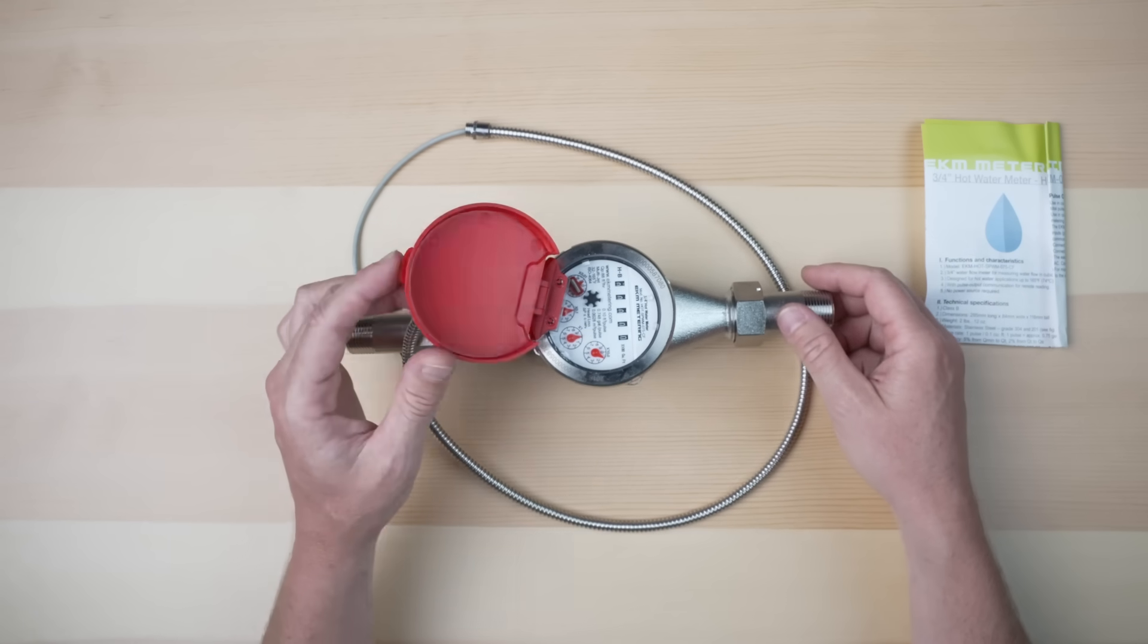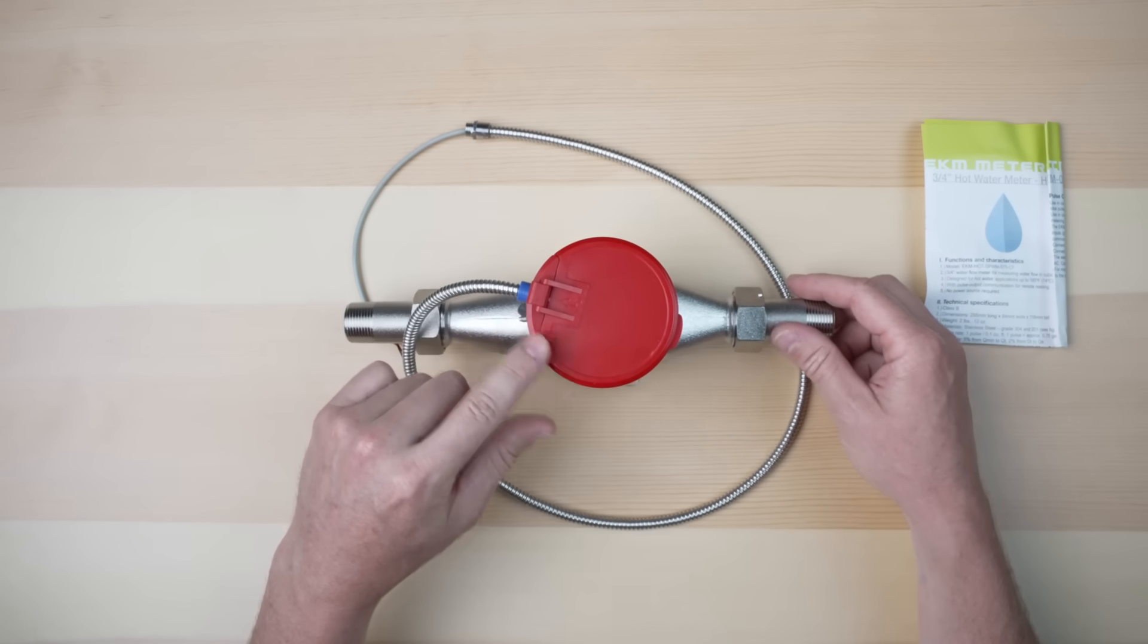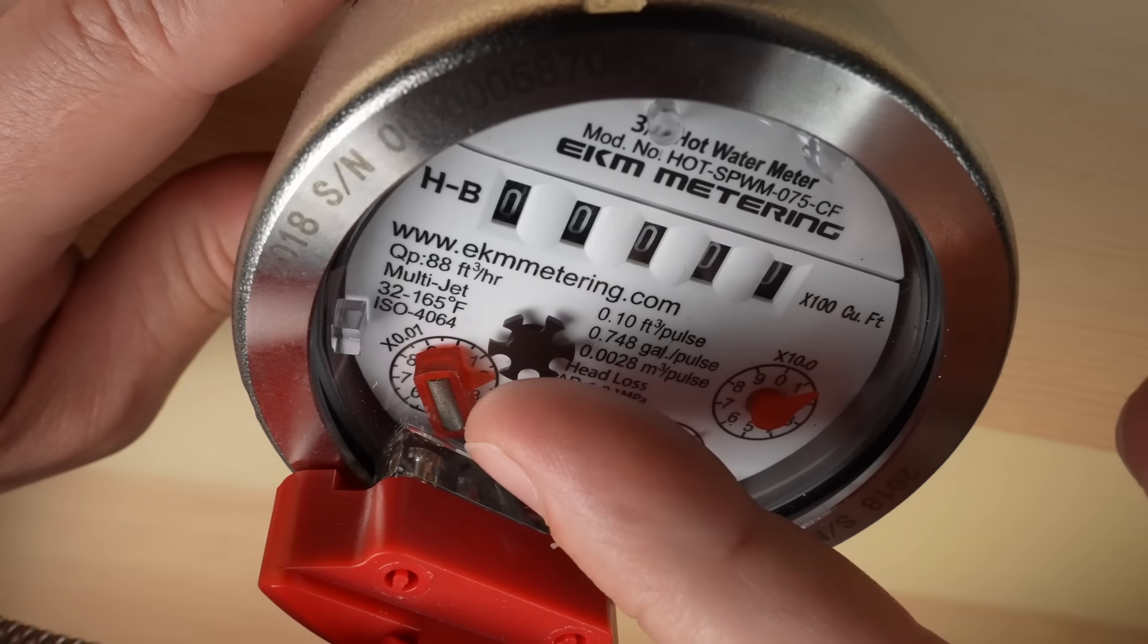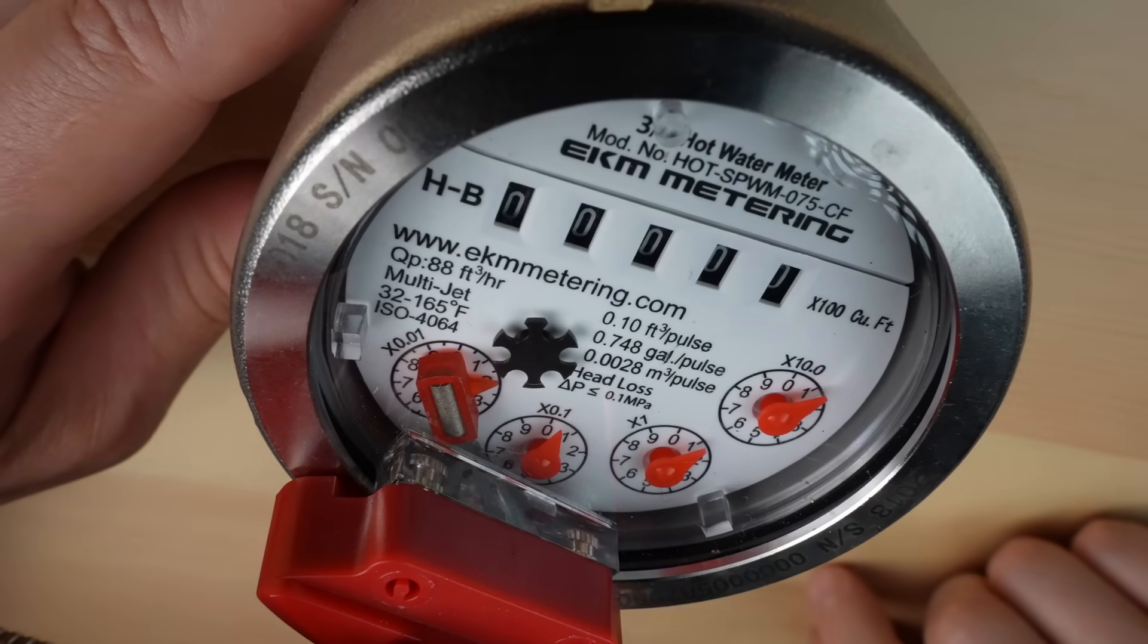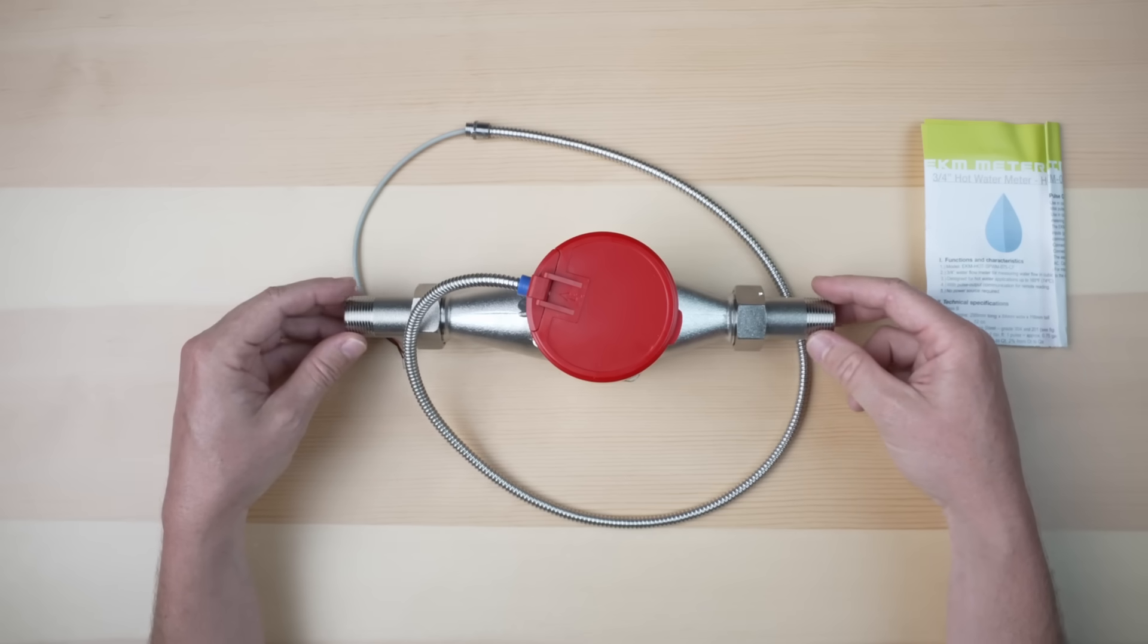The meter is remote readable via its pulse output, which is part of the lid mechanism. It generates a pulse for every tenth of a cubic foot that flows through the meter.